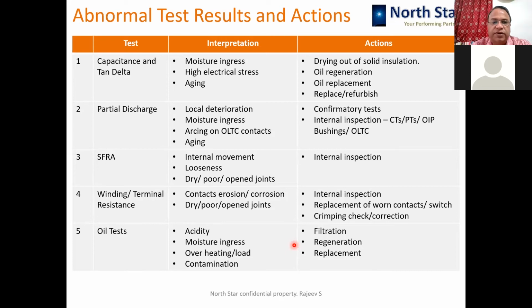partial discharge test. If it is failing in the partial discharge, it indicates inside local deterioration. There might be already a void or some other sharp point from where the insulation breakdown is happening. Moisture ingress also could be a reason, especially in small components like bushing, CTs, and PTs. Inside OLTC, if the arcing is happening, especially in tank OLTC, and aging of the insulation. So if we get a bad partial discharge result, then some confirmatory test is to be performed before taking any decision. An internal inspection of the transformer for any defects, CTPTs and OIP bushings and OLTC has to be done.